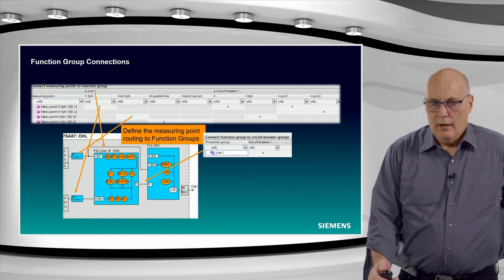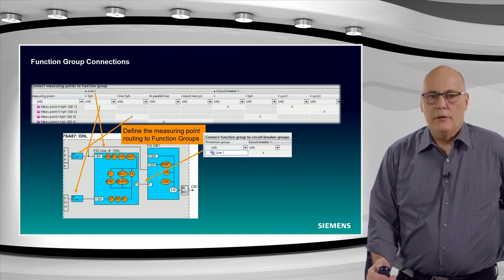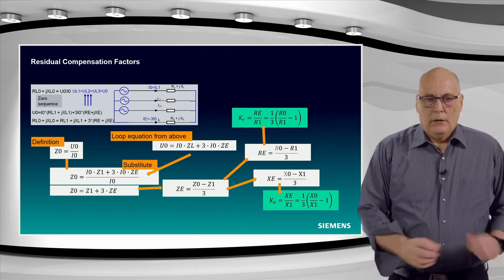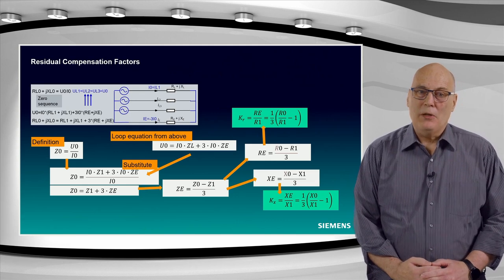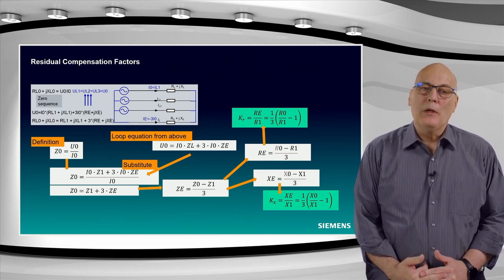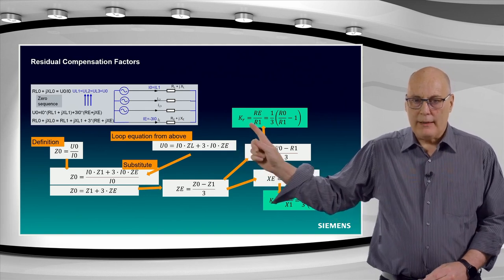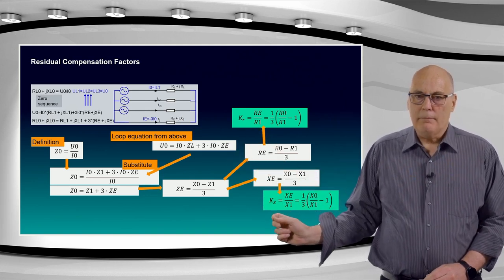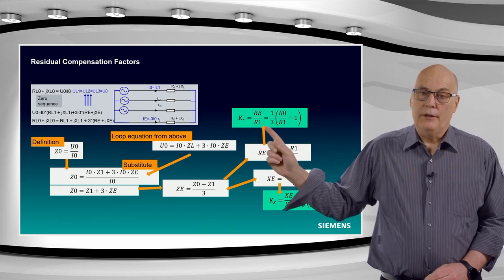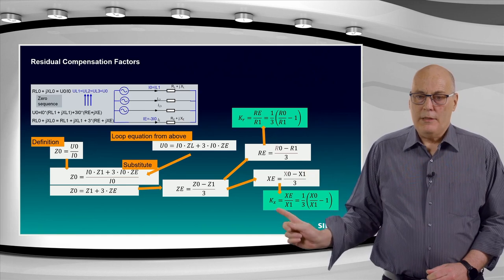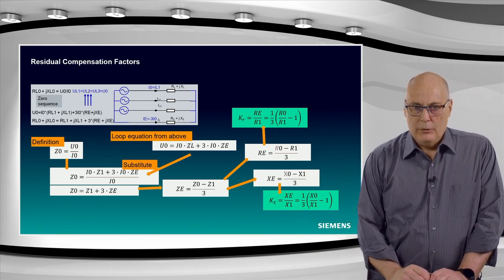But I think that's enough of that SIPROTEC 5 structure. Let's get back to the distance protection. And one of the key settings or things that one has to remember in distance protection is the so-called residual compensation factors. It's a name. Maybe you know them better as KR or KX here. Also, sometimes in SIPROTEC 4, you might know them as RE, R1. Well, I showed it here, RE, R1, XE, XL, or XE, X1. Your residual compensation factors, as we know that.